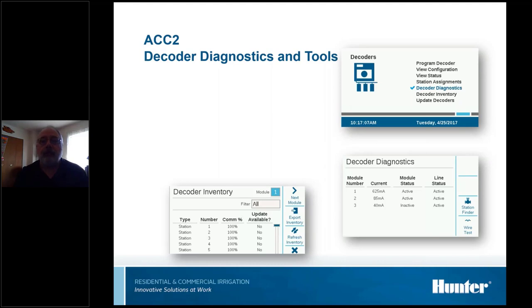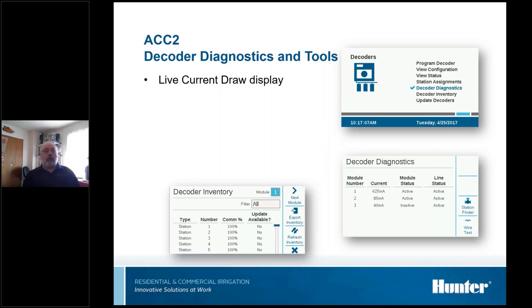So as far as the diagnostics on the ACC, and it's got quite a few of them, if you go to the decoder screen and then choose diagnostics, there's a whole bunch of different stuff we can do. So we get live current draw, and it's by module, and it's always there and it's live. In this case, it's showing you that module one's got a current draw of 625 milliamps. That's high. That's telling me there's a problem on that module.